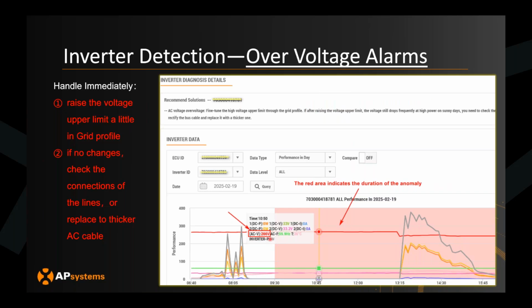One thing we can do on our end is expand those limits a bit higher, allowing power to be pushed through. But oftentimes those limits are already set high, and the issue is really the second option, which is to use thicker wire, because of the voltage rise effect. If you find that when the solar is producing and pushing power, the voltage increases quite significantly, it usually means you may need a thicker wire between the trunk cable and the AC combiner.